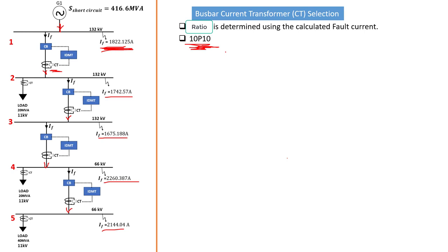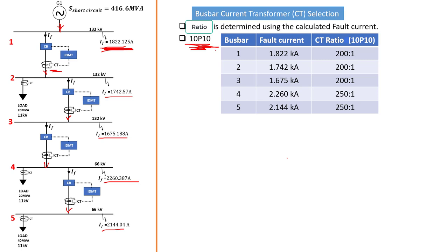That 10% margin of tolerance will actually ensure more reliability for your selected current transformer. Reliability is very important because you don't want to be sending false triggers into your relay coil, which would trip your circuit breaker even if there is no fault. You need a reliable system, so the margin of accuracy is important. That is basically what you need in order to select your current transformer. We then have the selected current transformer ratios based on the particular current on every one of these bus bars, with our selected accuracy factor limit.